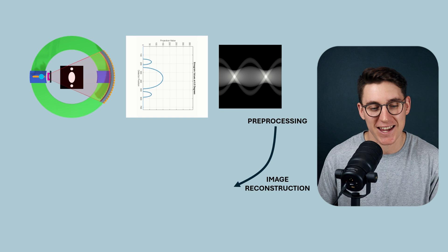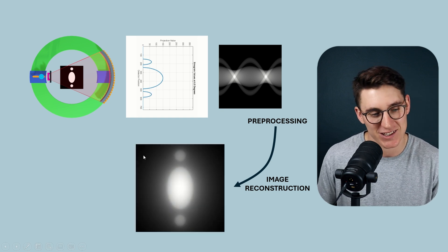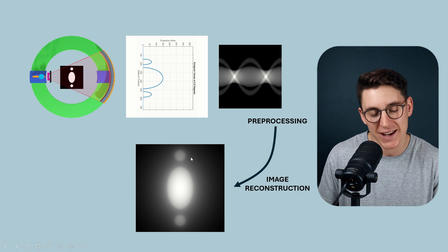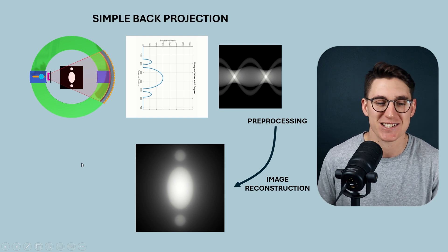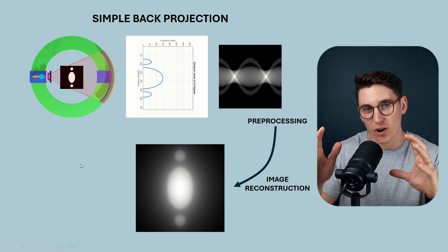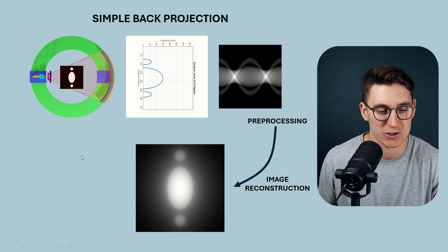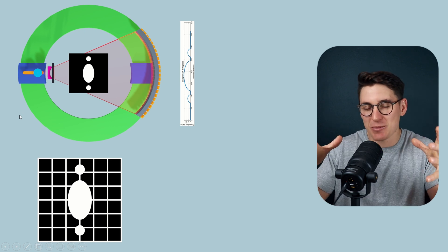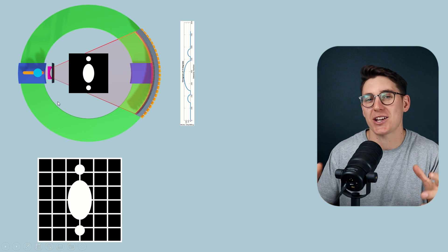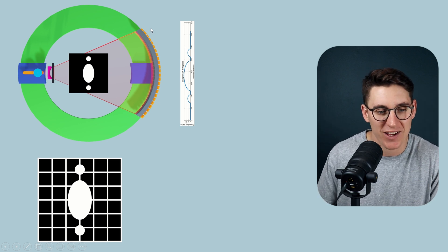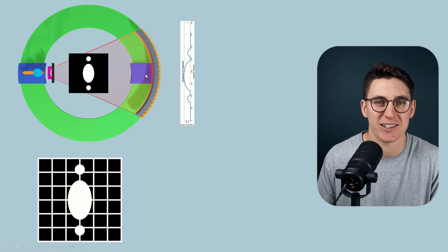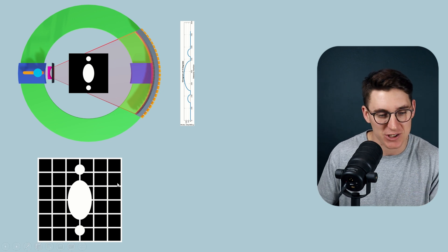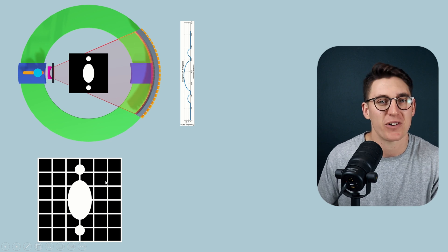The process we're going to look at today will generate an image that's not a perfect representation of what's actually happening within the patient, but we can see the underlying structures and where they sit. This process is known as simple back projection, and it will form the backbone for future image reconstruction techniques. When we're acquiring data, the CT machine has no idea what's sitting within it — the patient's anatomy is unknown. The only data we have is the transmitted X-rays hitting the detector. That's the eyes of the CT machine, and it's that data we use to calculate attenuation values.